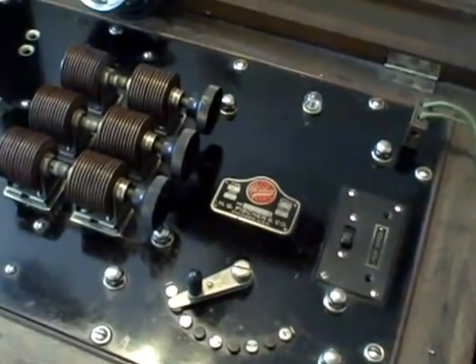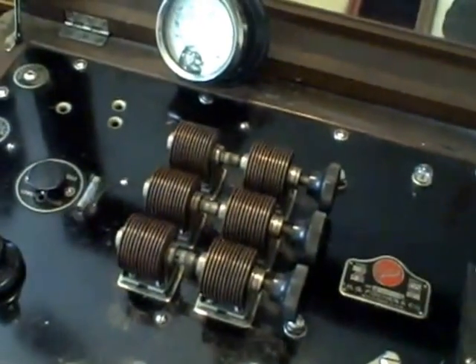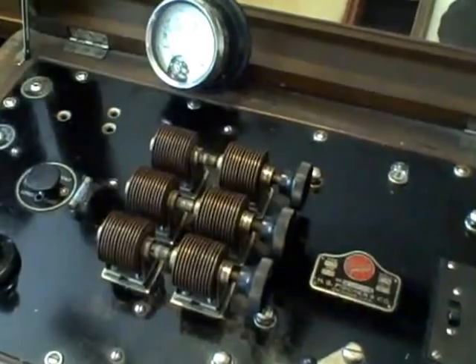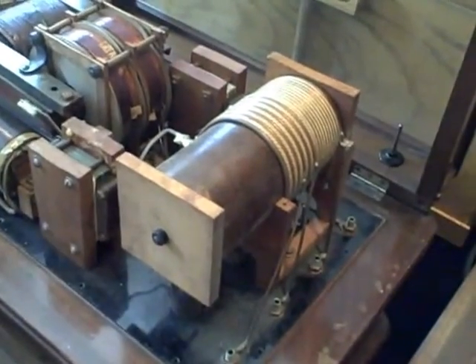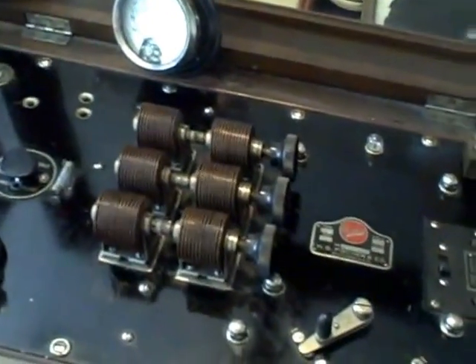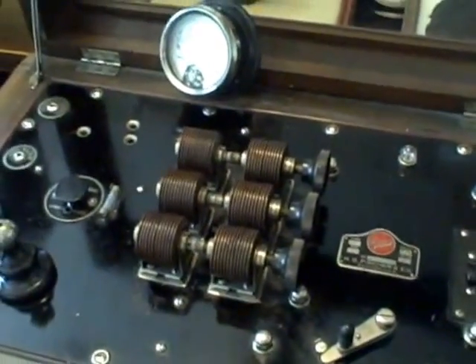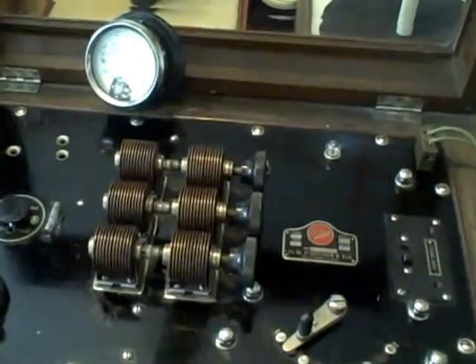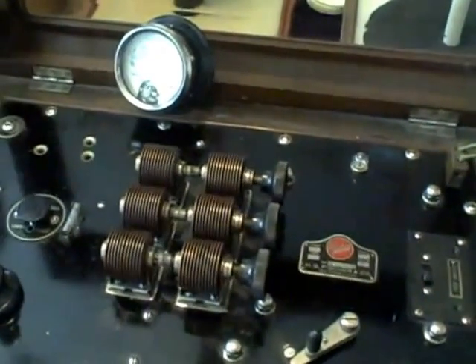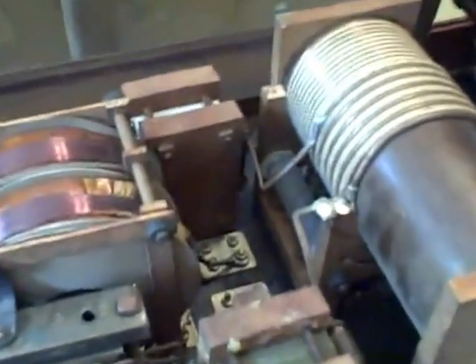In the 1940s, the only thing that changed with these machines was because of radio interference — they switched to shortwave and eventually radio tubes were powering the machines. The concepts stayed pretty much the same. But for surgical use, it's interesting to note that spark gap type Tesla coils are still used today. You can use solid state and tube driven circuits to power a coil, but you can't get the same degree of coagulation and cutting ability that you can with a spark gap circuit. That's because of the damped oscillations versus undamped oscillations and how physiologically the tissues react to them.